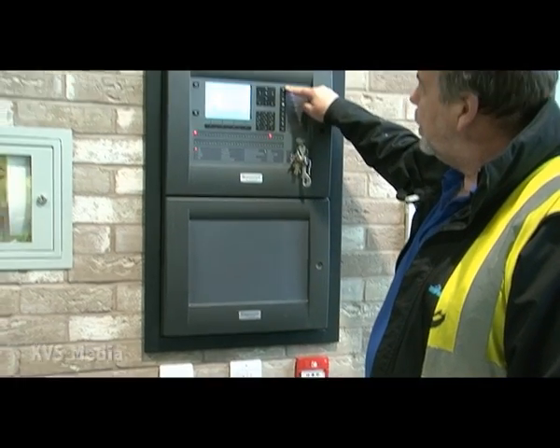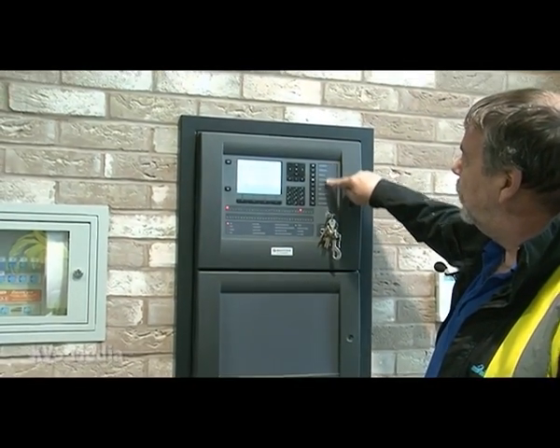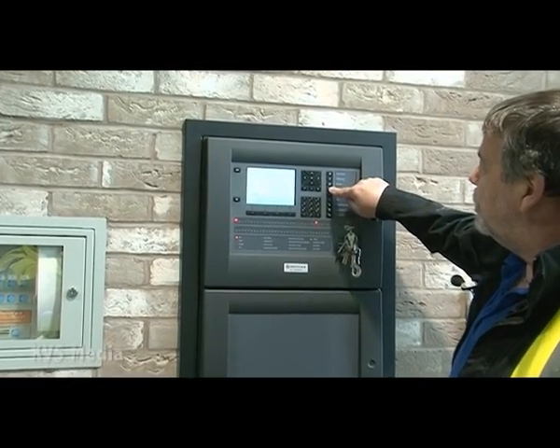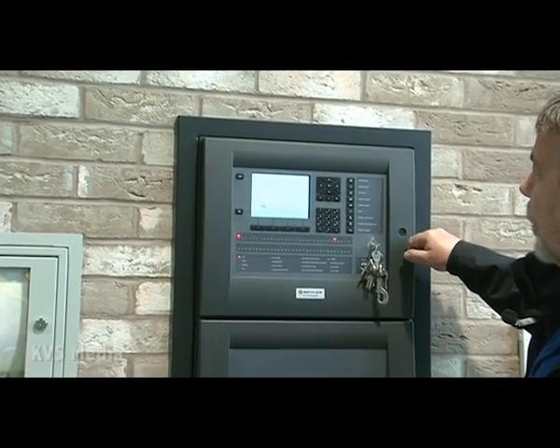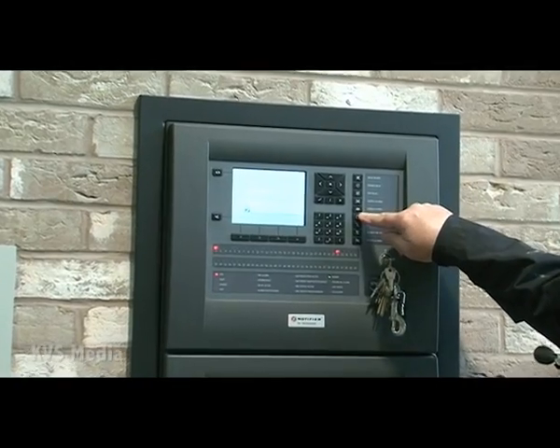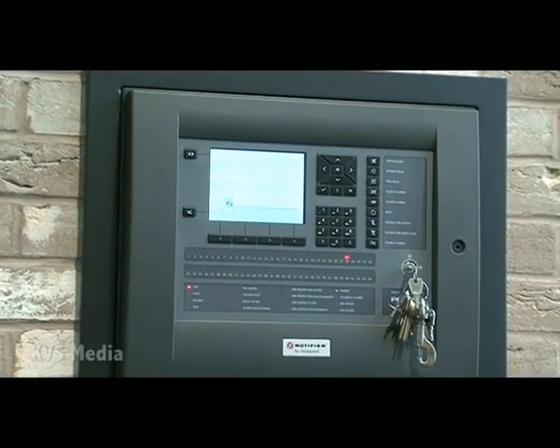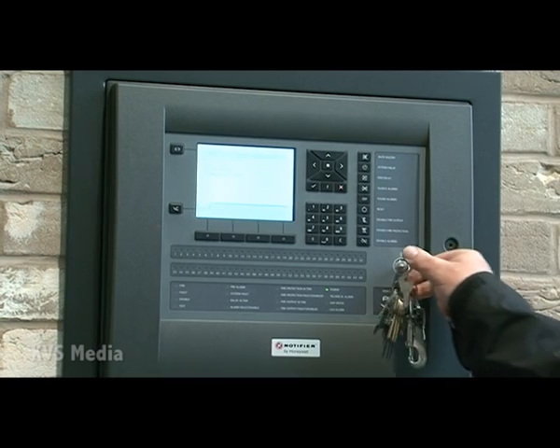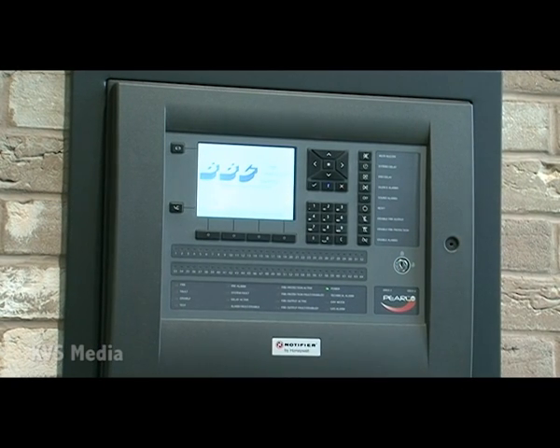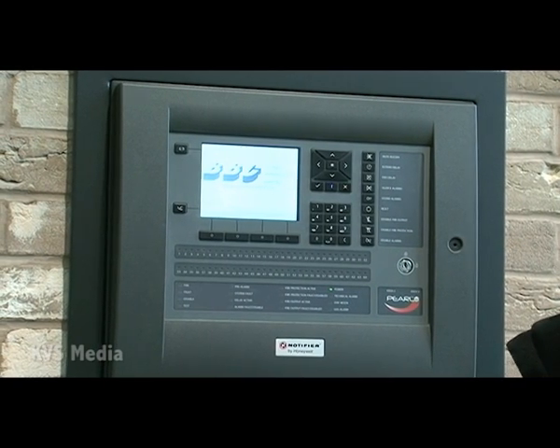And then on the panel we can mute the internal buzzer, silence the alarms, and ultimately we can then press the reset button, which should take us back to a system normal, and remove the key. And that is basically how you go about a weekly test.